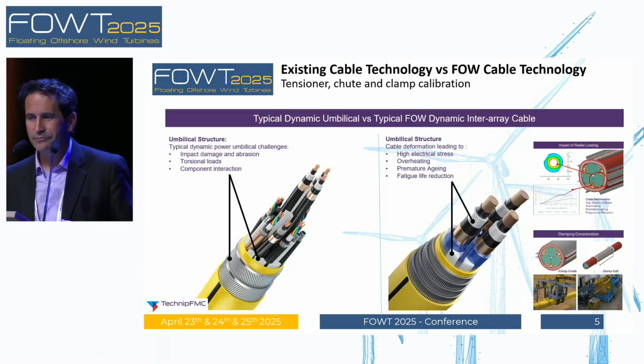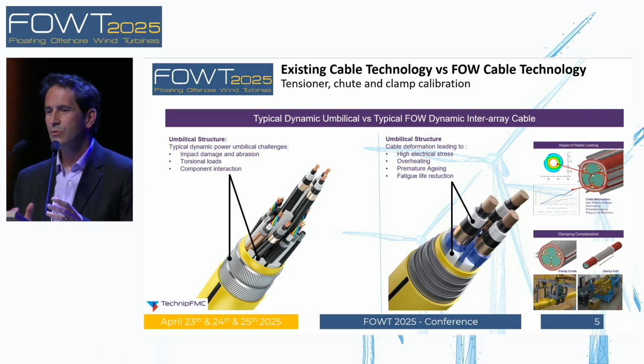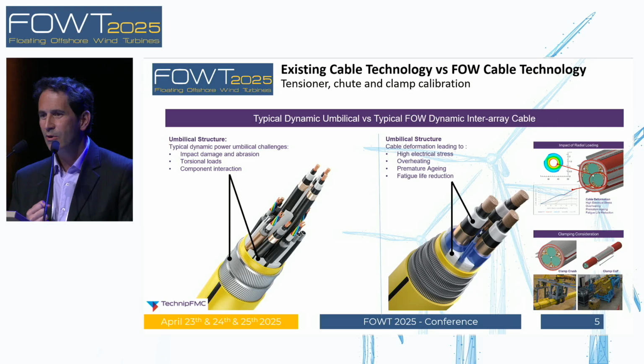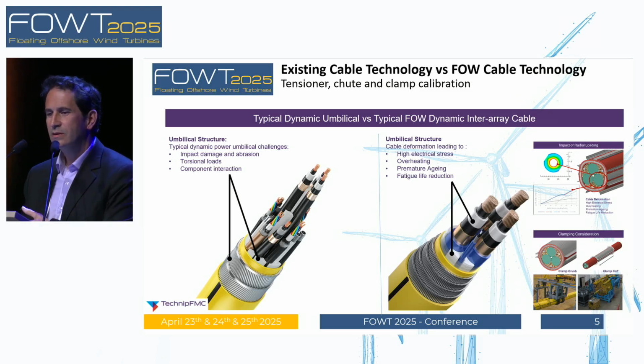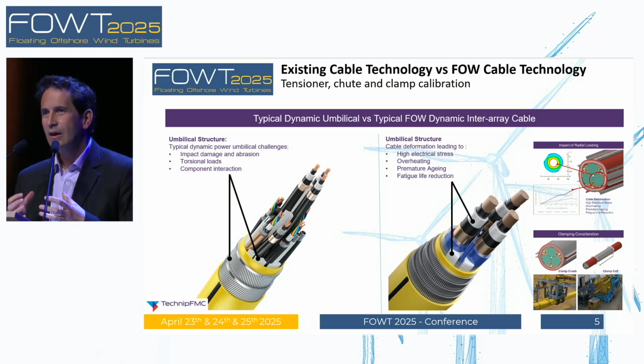So what's different? If you look at the two cross sections here, it's quite obvious. The size of the conductor is much smaller, and therefore there is quite some conservatism in the insulation layer, among other things, that puts the conductor in a safe place. The conductor on umbilicals is also surrounded by a full bundle, which makes the compression or the loading that we apply to it during handling and installation a bit more gentle. When you look at the right-hand side, you've got the dynamic cables, where it's fully mobilized under the compression of the tensioner, the clamp, or whatever you attach to it, and therefore it's immediately in contact with the loading. So I'm not saying it's dangerous, I'm saying it needs to be properly designed and assessed.